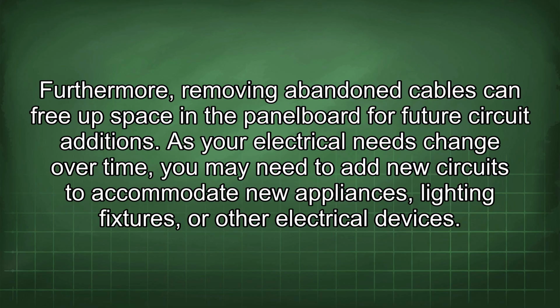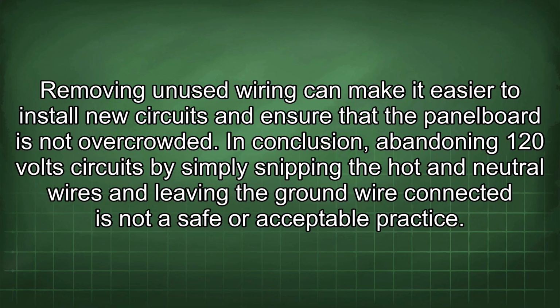As your electrical needs change over time, you may need to add new circuits to accommodate new appliances, lighting fixtures, or other electrical devices. Removing unused wiring can make it easier to install new circuits and ensure that the panel board is not overcrowded. In conclusion, abandoning 120-volt circuits by simply snipping the hot and neutral wires and leaving the ground wire connected is not a safe or acceptable practice.